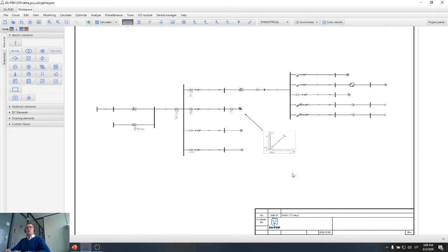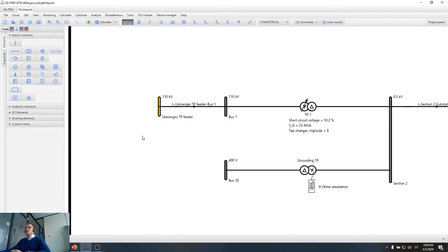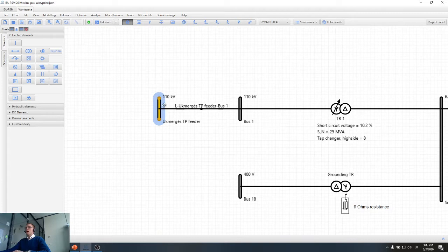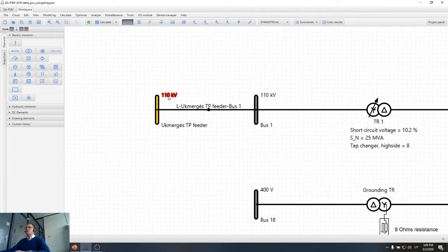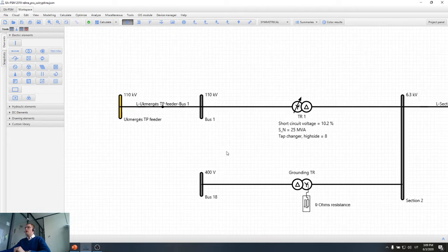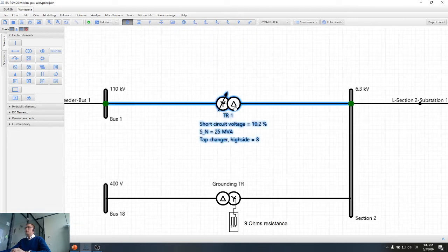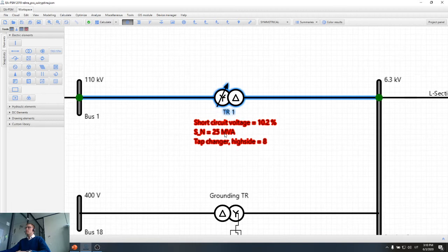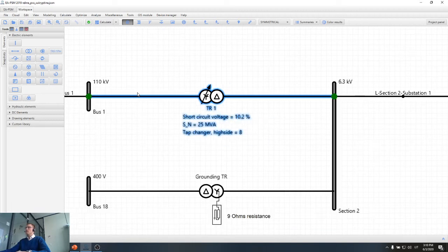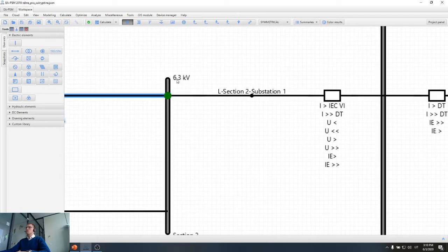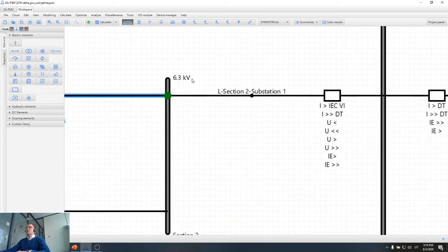So to begin with, first of all, let's look at the electrical network. So short introduction about the network. Network starts from high voltage side, so it's 110 kilovolts network. Then we have a transformer, 25 megavolt-ampere transformer, which reduces voltage from 110 to the medium voltage level 6.3 kilovolts.